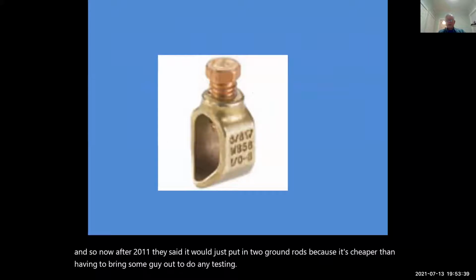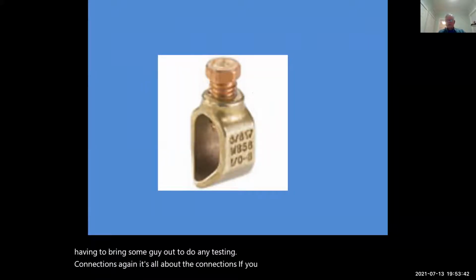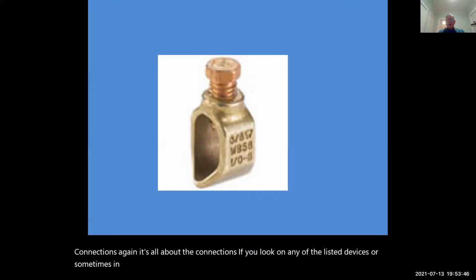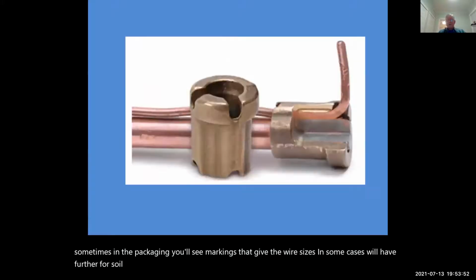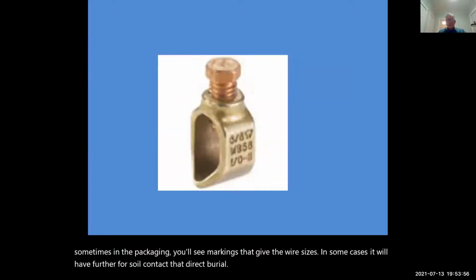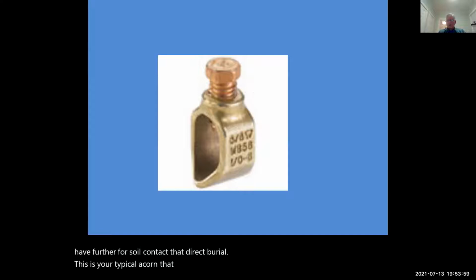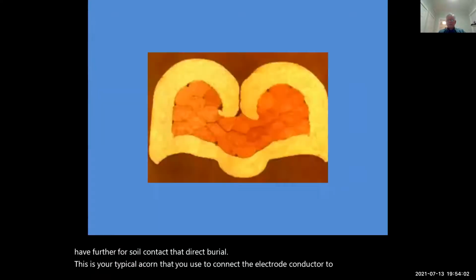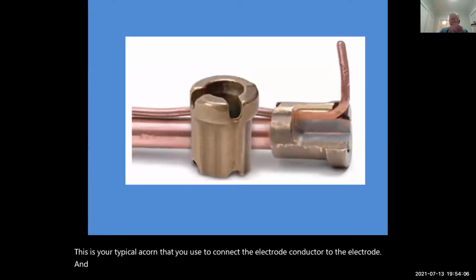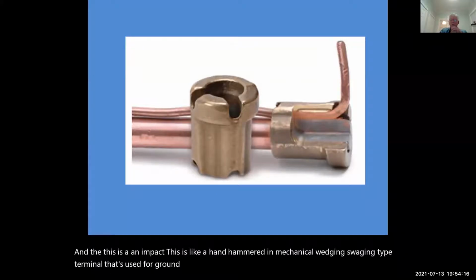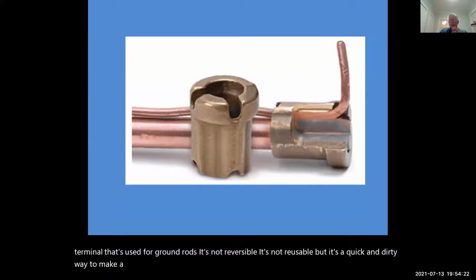Connections, again, it's all about the connections. If you look on any of the listed devices or sometimes in the packaging, you'll see markings that give the wire sizes. In some cases, it'll have for soil contact, direct burial. This is your typical acorn that you'd use to connect the electrode conductor to the electrode. This is an impact type terminal, like a hammered-in mechanical wedging, swaging type terminal that's used for ground rods. It's not reversible, it's not reusable, but it's a quick and dirty way to make a connection, as long as you have one that's listed for direct soil contact.